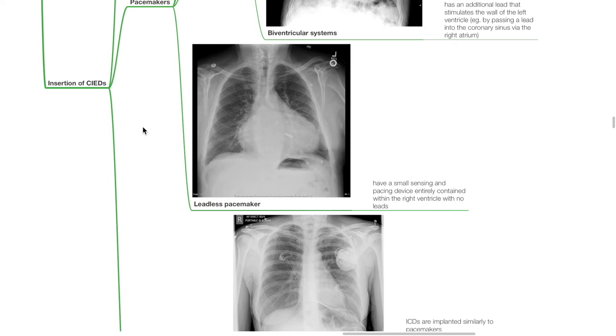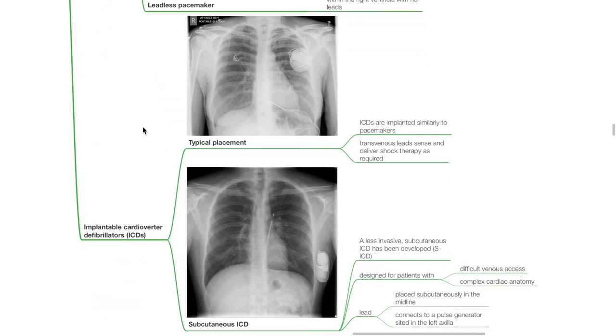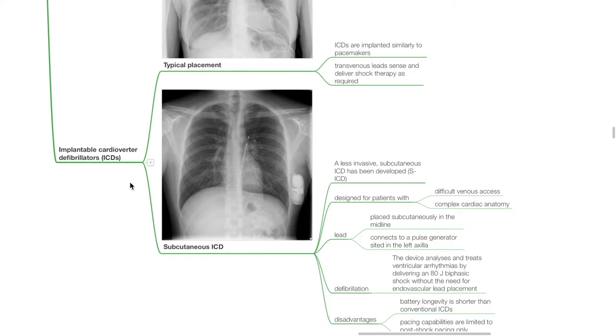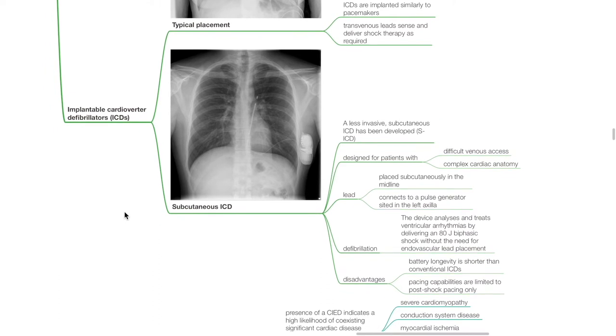Leadless pacemaker: this is a small sensing and pacing device entirely contained within the right ventricle with no leads. ICDs: typical placement involves ICDs implanted similarly to pacemakers, with transvenous leads that sense and deliver shock therapy as required. Subcutaneous ICD is a less invasive version designed for patients with difficult venous access or complex cardiac anatomy. The lead is placed subcutaneously in the midline and connects to a pulse generator sited in the left axilla. The device analyzes and treats ventricular arrhythmias by delivering an 80 J biphasic shock without endovascular lead placement. Disadvantages include shorter battery longevity than conventional ICDs, and pacing capabilities limited to post-shock pacing only.